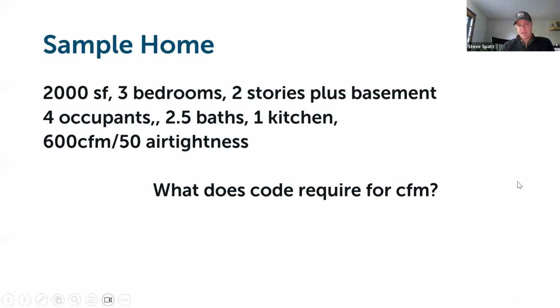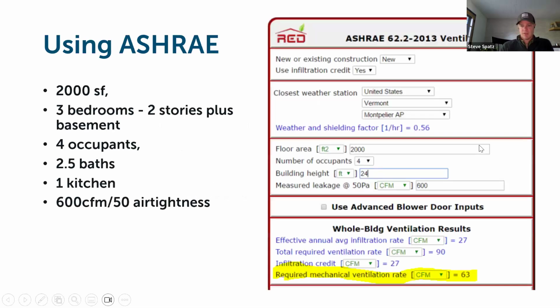So we'll walk through this as an example. The example that we'll use to show you how this tool works and how to get to the idea of designing the whole system is a 2,000 square foot house, 3 bedrooms, 2 stories plus a basement, 4 occupants in the house, 2.5 baths, a kitchen, and blower door testing done on the building with a result of 600 CFM at 50 pascals of air tightness. So that's the amount of air moving through the building envelope from an air leakage standpoint. So we'll use the ASHRAE REDCalc tool to do our calculations here for this specific building.